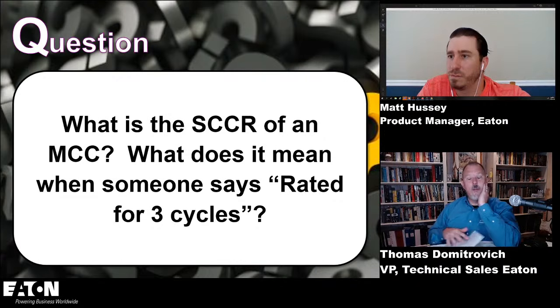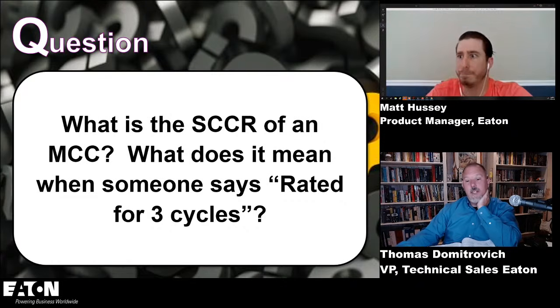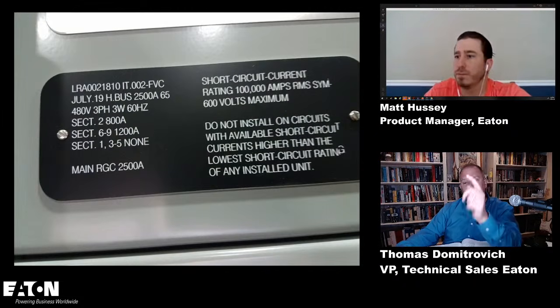Okay, so let's talk about short circuit current ratings. What do you think? You ready for that, Matt? So what is the short circuit current rating of an MCC, and what does it mean when someone says rated for 3 cycles? Now, I'm looking at this label. Do you put this on all MCCs? Yeah, that's what we would call a master nameplate. But you can see there's the short circuit current rating identified there.